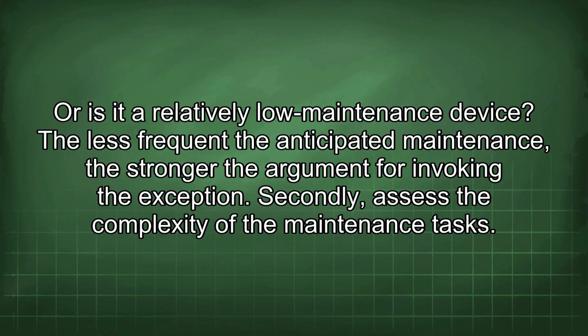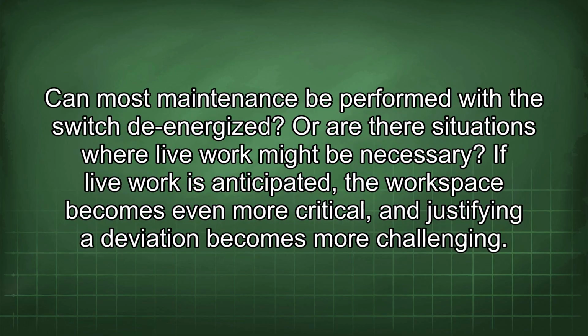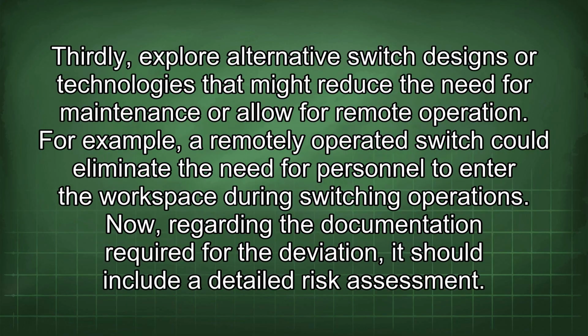Secondly, assess the complexity of the maintenance tasks. Can most maintenance be performed with the switch de-energized? Or are there situations where live work might be necessary? If live work is anticipated, the workspace becomes even more critical, and justifying a deviation becomes more challenging. Thirdly, explore alternative switch designs or technologies that might reduce the need for maintenance or allow for remote operation. For example, a remotely operated switch could eliminate the need for personnel to enter the workspace during switching operations.